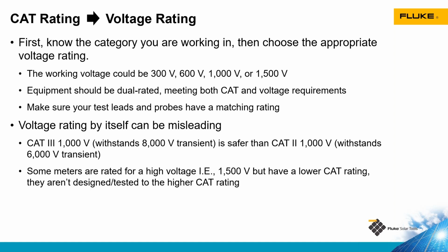Different voltages within the same different category levels make a difference on how large of a transient the tool can withstand. Here we've got a Category 3 1,000 volt tool is designed to withstand 8,000 volt transients, where a Category 2 1,000 volt tool can only withstand 6,000 volt transients.